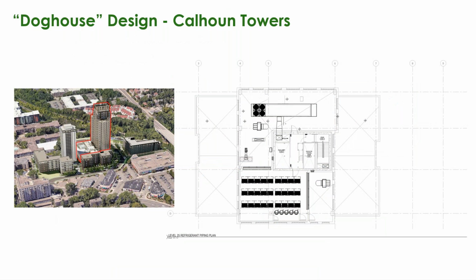Another one in Minnesota was a retrofit of an old hotel that wanted to switch to a variable refrigerant system, but they didn't have a lot of space to put these units on rooftops around there, and they had 24 stories to deal with. So they opted that the juice was worth the squeeze to build a penthouse mechanical room and put all of the condensing units up there and do a doghouse on the top of the building, serving everything down below from above.